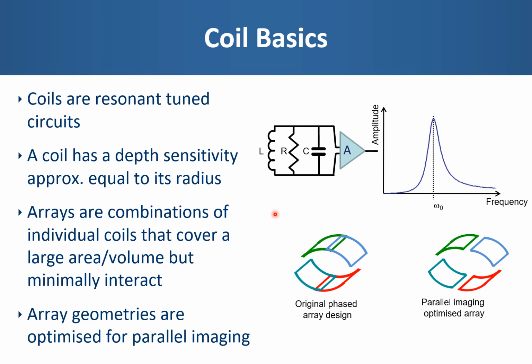As already mentioned, receiver coils are generally made of several small individual coil elements. Each coil element is sensitive to a small volume of interest, thereby minimizing the amount of noise that is detected. But the use of multiple elements ensures that we have the desired coverage. The original coil arrays, known as the phased array designs, required that the elements be appropriately overlapped, so there was minimal mutual interaction or induction between the coil elements, so that the response from the individual coils just did not appear to come from one large single coil. As the number of elements in coils has increased, there is now generally some spatial separation between them. This variation in spatial sensitivity profiles allows for more advanced acquisition and reconstruction methods that can be used to accelerate MR image acquisition.